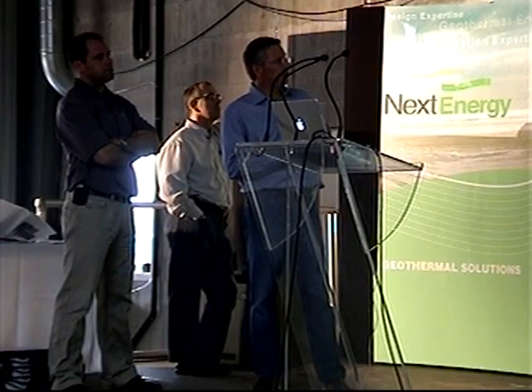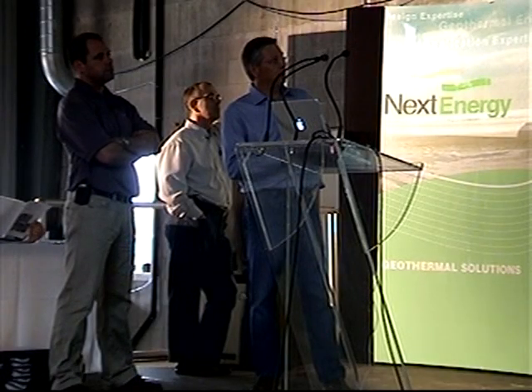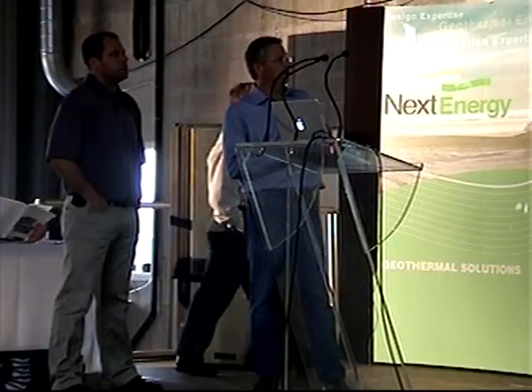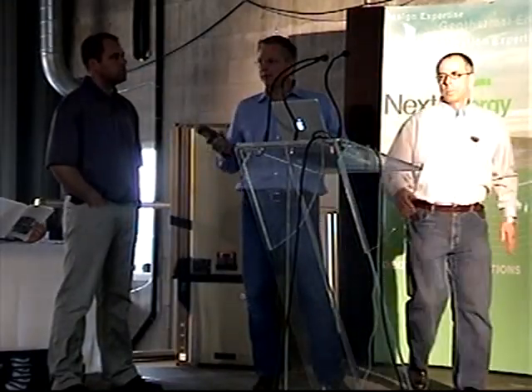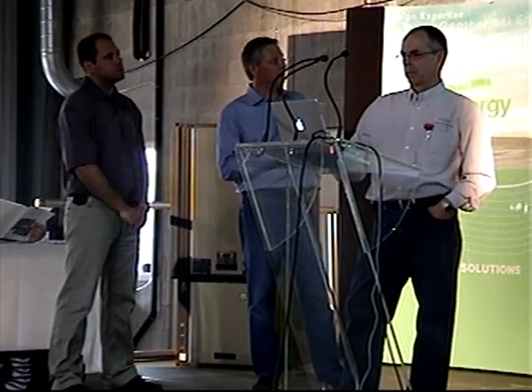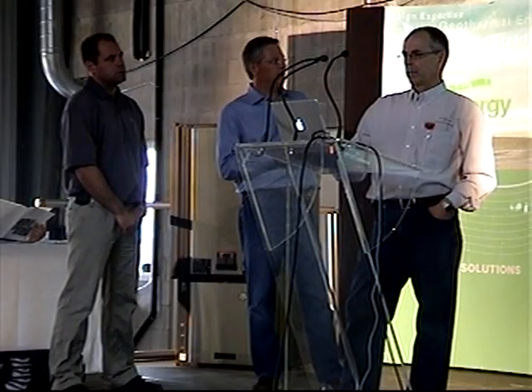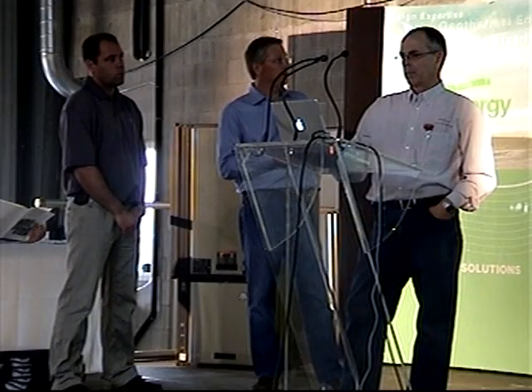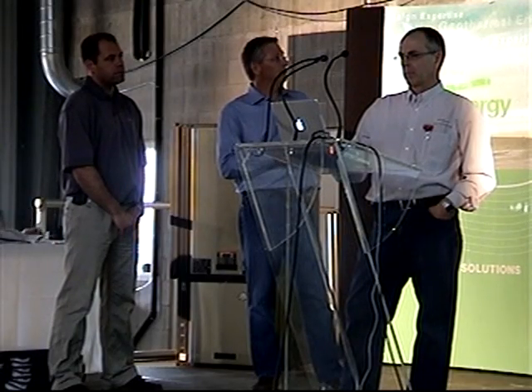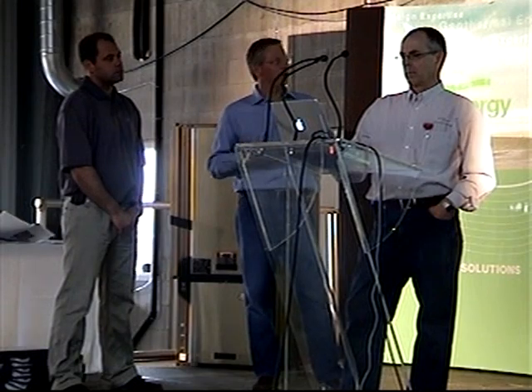And if you're in test mode, you'll see these fault codes, and you'll see them at the stat. If there's no fault at all, you'll just get 1 blink. That means the unit's never had a fault. Then 2 flashes means a high pressure fault. 4 is the one that you might see the most. 3 means a low pressure, that's loss of charge. You almost never see that.